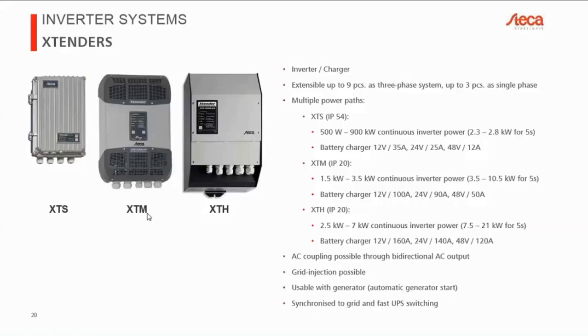Of course, this is fully up to you. You can program the inverter not to inject into the grid, but some energy providers are more picky than others. So this is a case where you need to basically prove to them that you're not, or that if you're injecting, that you're injecting according to the law. So that's one difference. You can mix AC input and DC, or basically battery energy or PV energy.